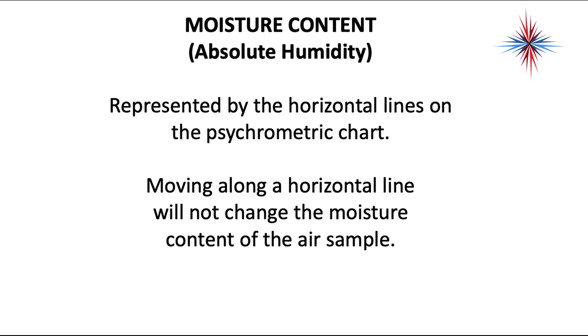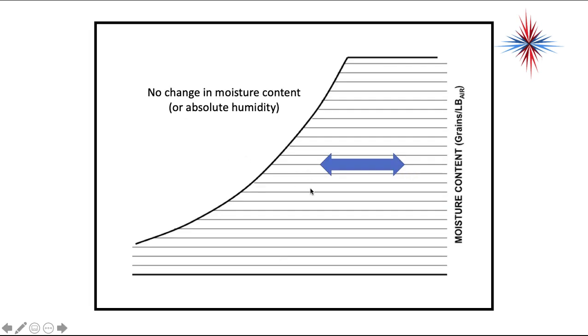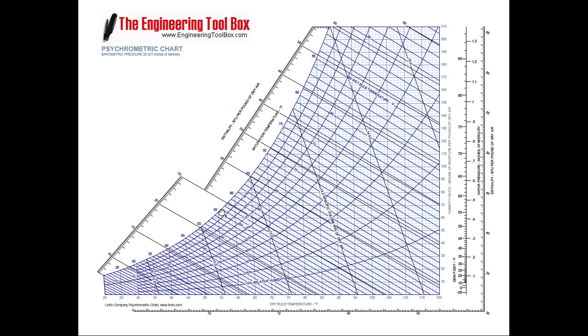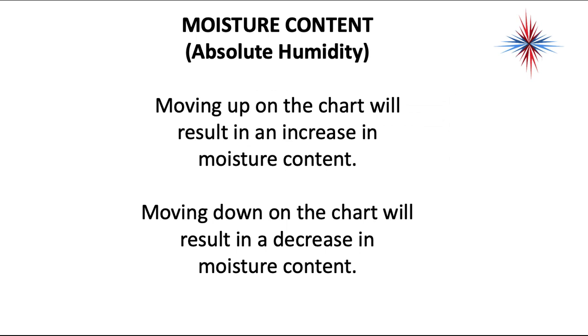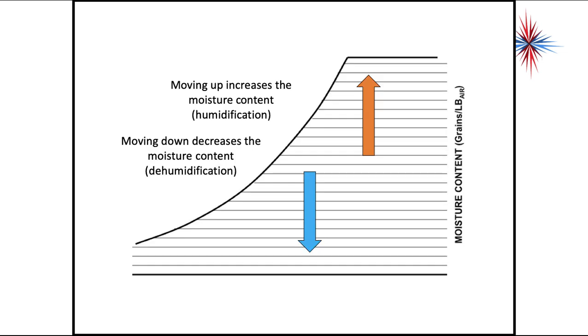Moisture content is also on the chart. It's represented by horizontal lines on the psychrometric chart. Moving along a horizontal line will not change the moisture content of the air sample. The scale for moisture content is on the right side. If you go any place left to right along the line, you don't change it. Moving up on the chart will increase the moisture content — humidification — and moving down will decrease it — dehumidification.